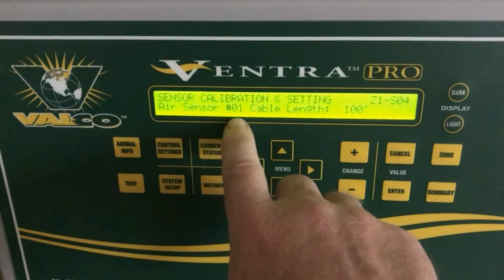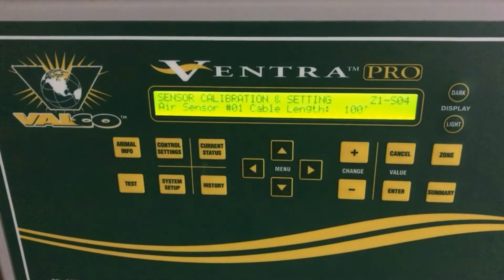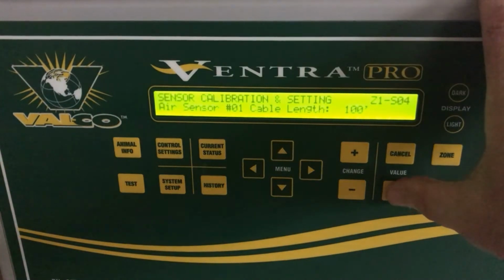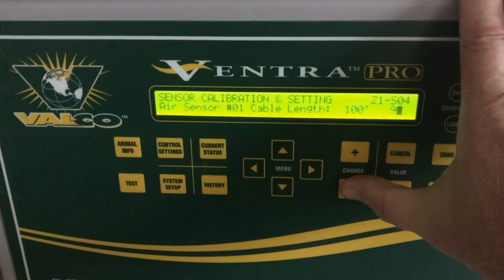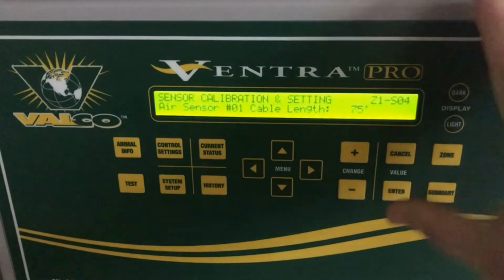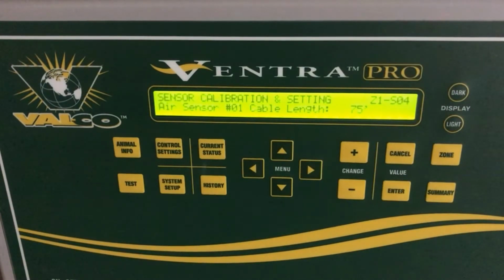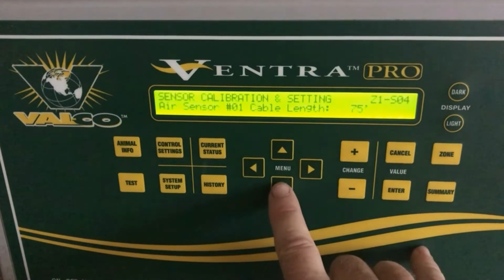The first thing we choose for temperature sensor 1 is the cable length. It is important to know how much cable or wiring you have run from your controller to your temperature sensor. In this case, it's about 75 feet. So I change it to 75 foot. And this is important because the controller uses the amount of wire run to help configure the temperatures. So to have the most accurate reading possible, you want to have your cable length as close to exact as you can. Then you menu arrow down.